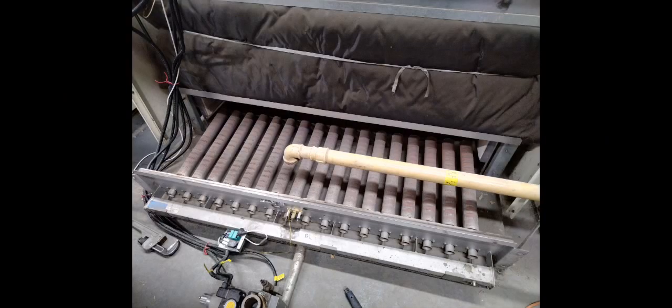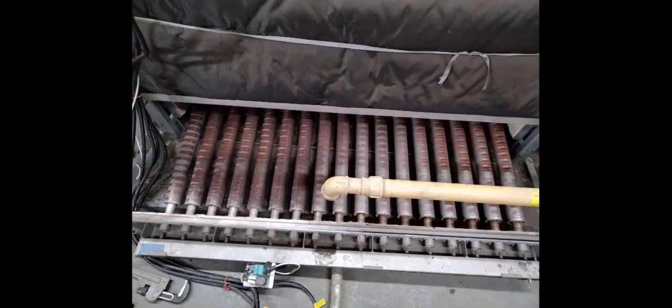So I disconnected my union on my gas valve and obviously isolated the gas supply, pulled the burner out. It's not easy, it does have some wheels, but it's still not easy to pull it out. I wheeled it out and then cleaned down the burners. I used some water on it to get down some of the dust and also just a light brush.